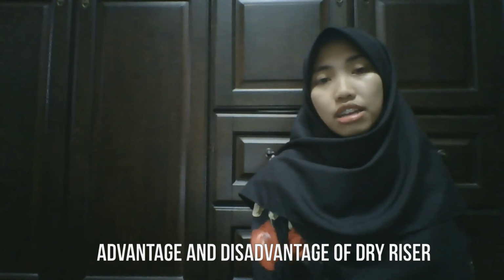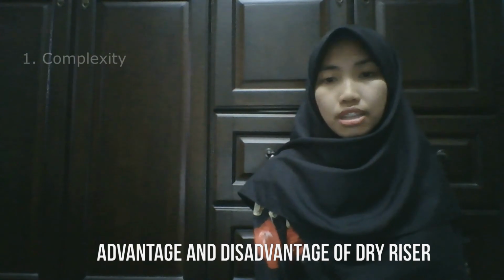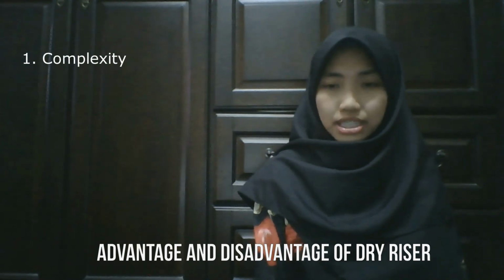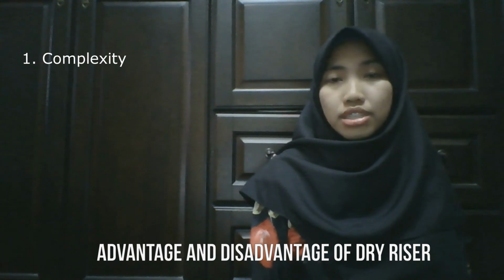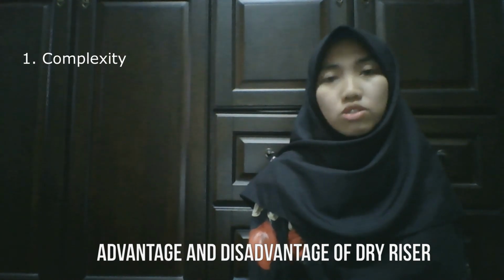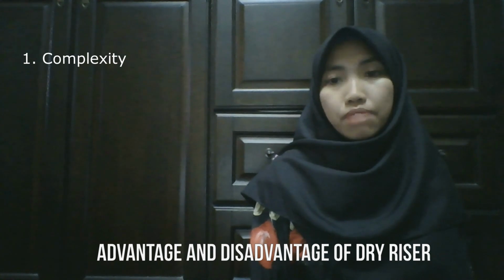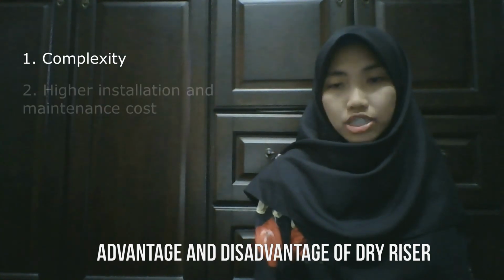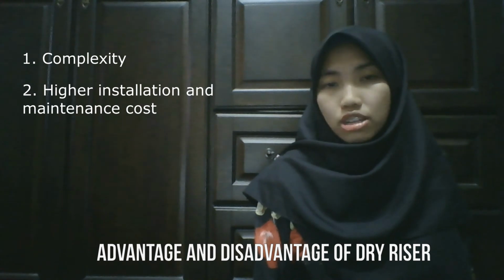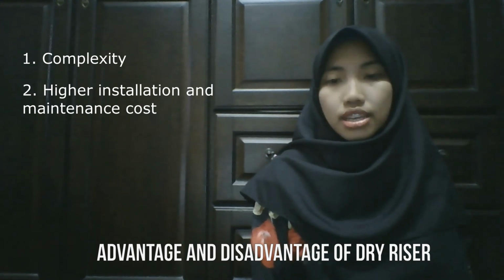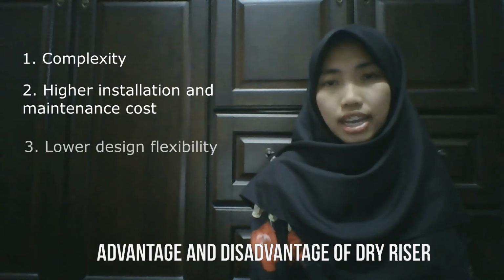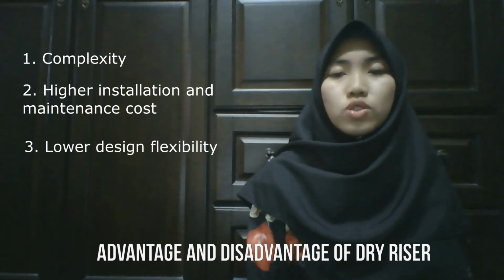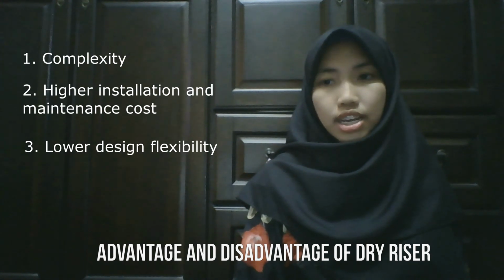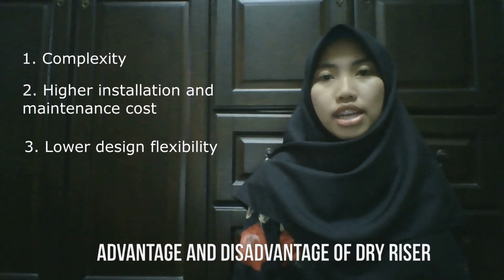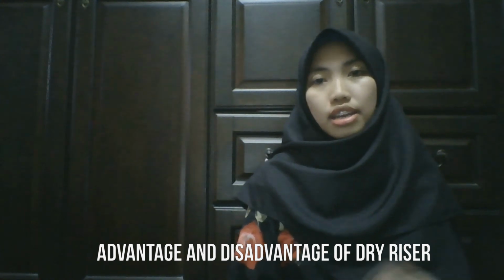Next are the disadvantages of the dry riser system. It has increased complexity as the dry pipe system requires additional control equipment and it uses air pressure or nitrogen to hold back the pressure. Second, it has higher installation and maintenance costs. Third, it has lower design flexibility. This is due to the restriction regarding the system size. So additions to the system can make it difficult or not possible.